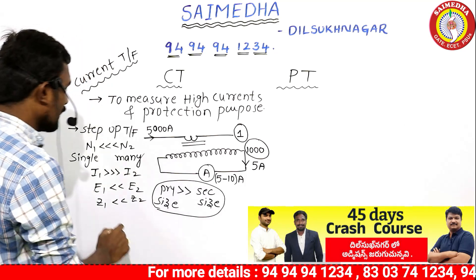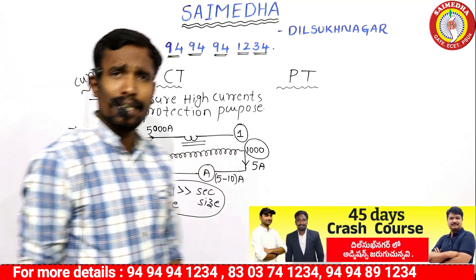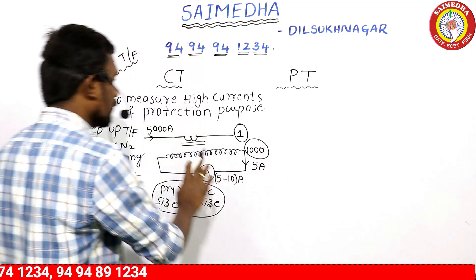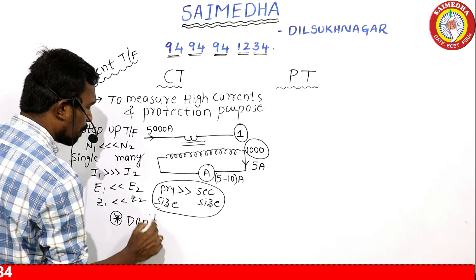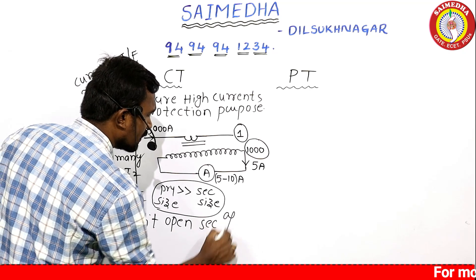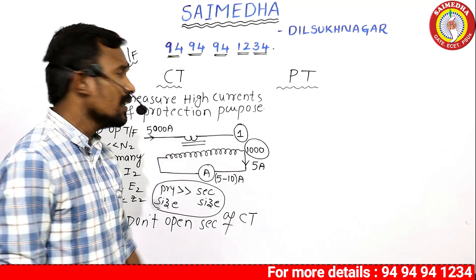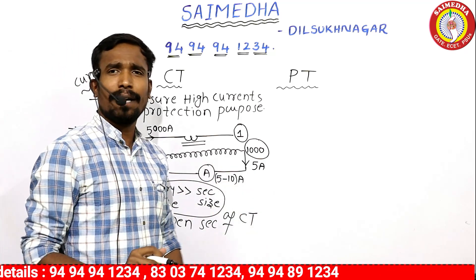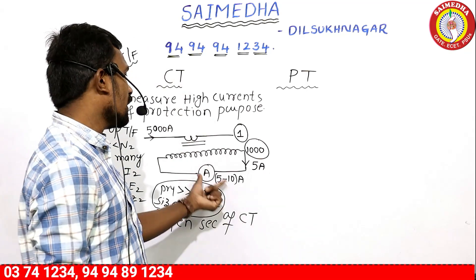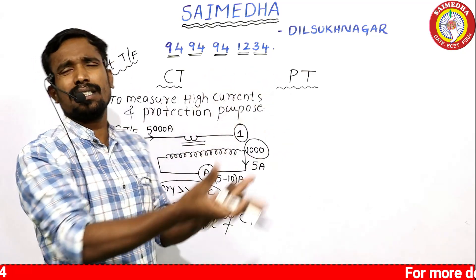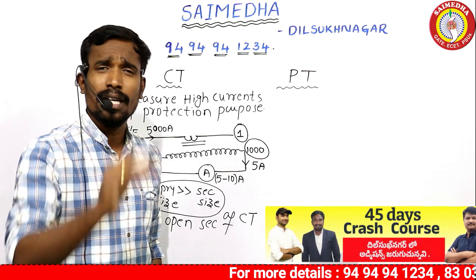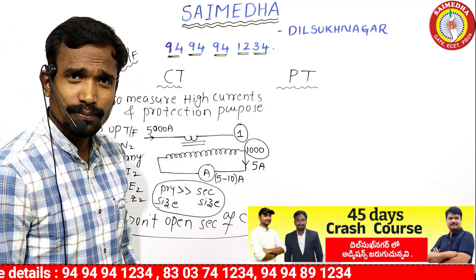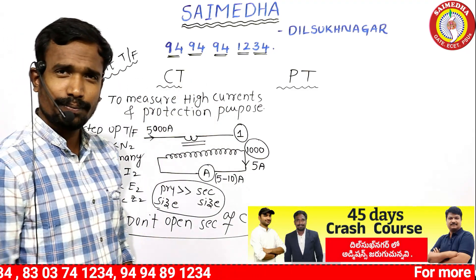Very important point — this was a question in SPDCL 2022: In a transformer, the high voltage winding is open-circuited and the high current winding is short-circuited. For CT, do NOT open the secondary. Always short-circuit the secondary of the CT; otherwise, very high voltages will be induced, causing winding and equipment damage.